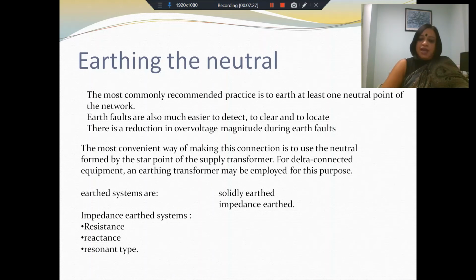Earth systems can be of two types. One is solidly earthed, the other is impedance earthed. Solidly means you do not have any resistance or any impedance between the neutral and the earth point. In impedance earthing, you have an impedance between the neutral point and the earth. The impedance earth systems, of course, can be of three types: the resistance earth, reactance earth, and resonant type.